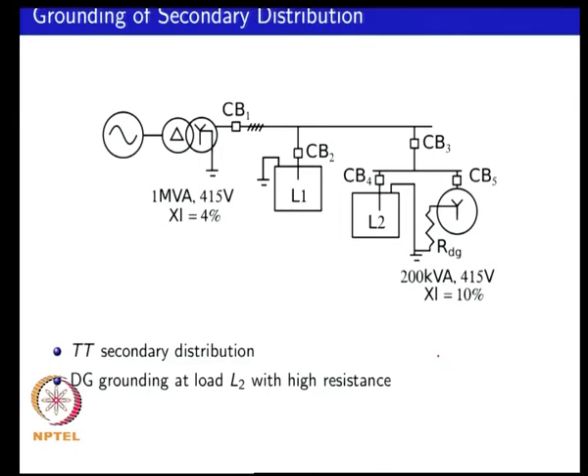If you look at this particular example, ignoring the DG for now, this is essentially a TT distribution secondary where the source is grounded directly to terra earth and each load has its own grounding electrode. Load 1 and load 2 ground wires are connected to earth. The DG is connected at load 2 with a resistance. So overall this is a system which has both TT aspects and also high resistance grounding aspects. In an actual system it is possible to have multiple grounding options present in the same system depending on your objectives.